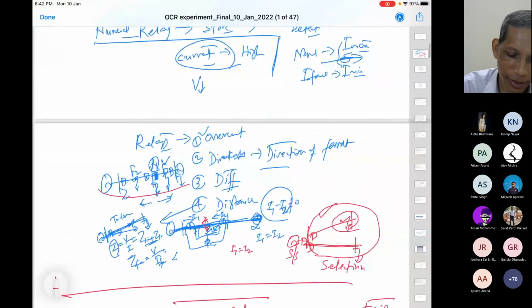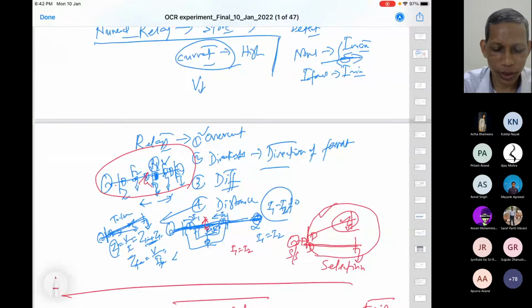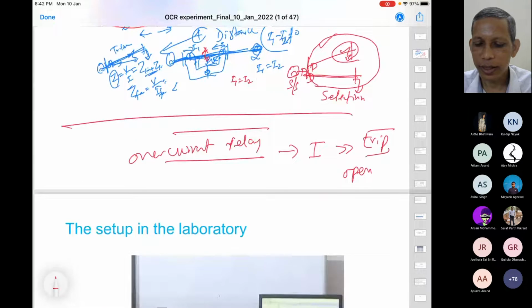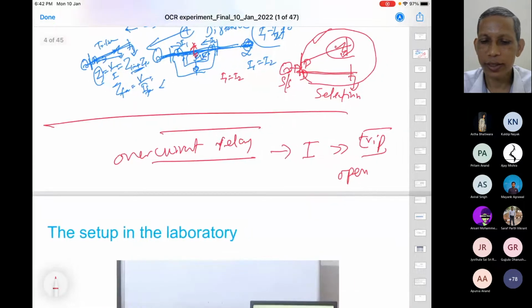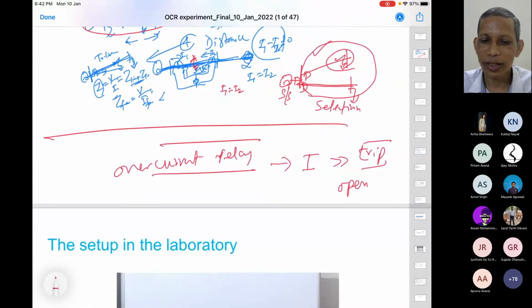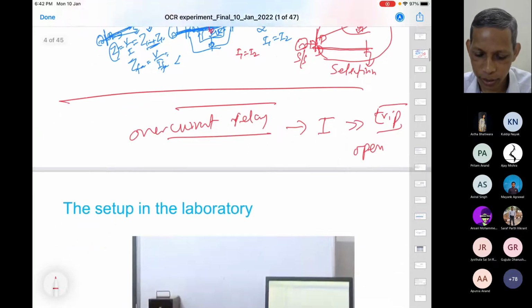Yeah, in this case, if any fault happens in this whole region, I can put a breaker here and trip the whole thing. Then all loads will be affected. So that is not desirable. Therefore, in the selectivity sense, we like to isolate the faulted section only, not the rest, so that maximum customers can still be retained in the system.